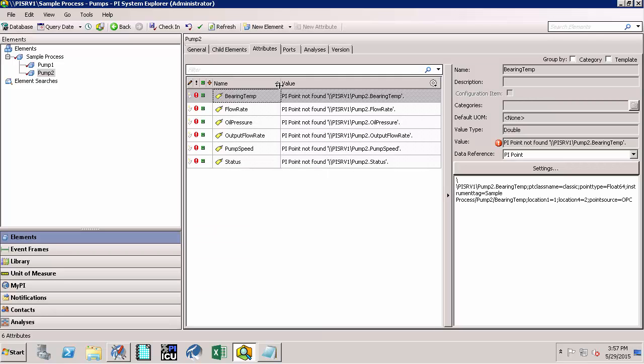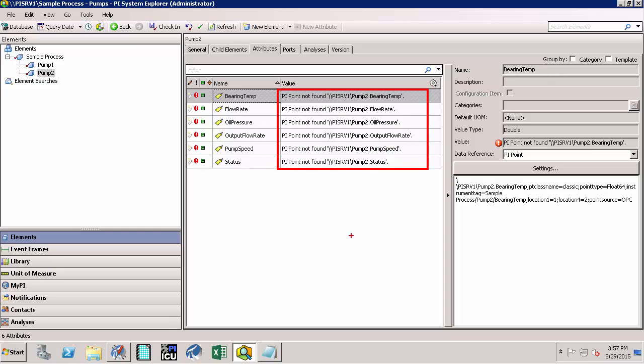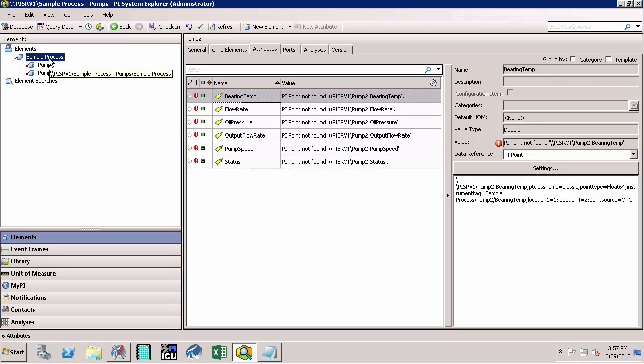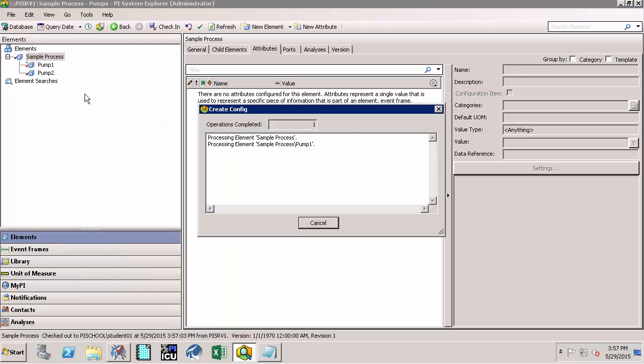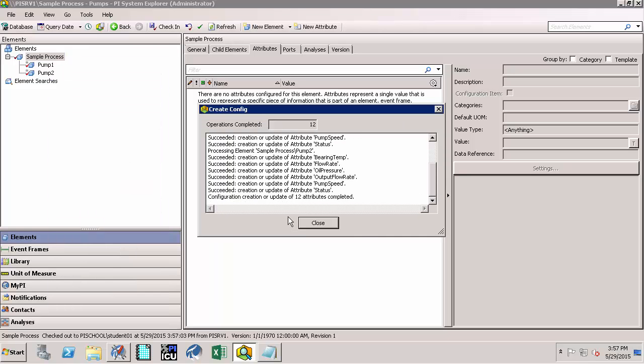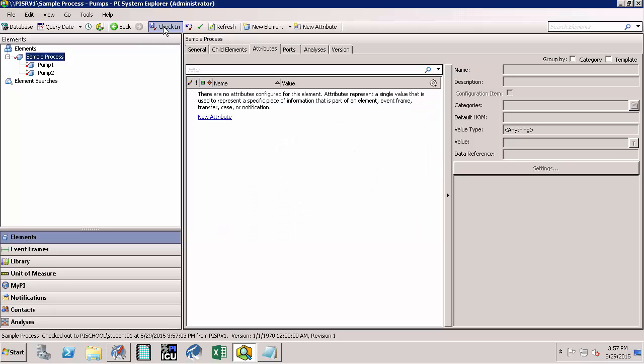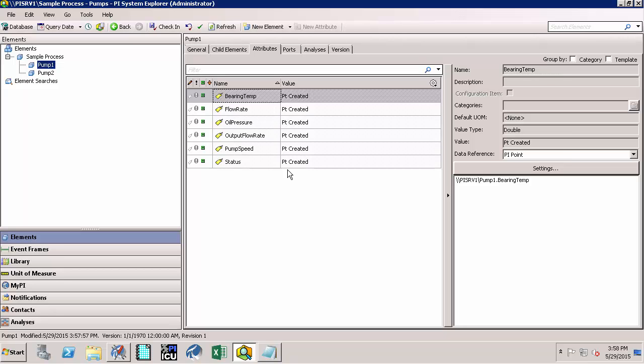Now let's go to the Attribute tab — we would note none of the PI Tags have been created yet. To create the PI Tags, right-click on Sample Process and say Create or Update Data Reference. By this process we have created all the tags associated with all the attributes for Pump 1 and Pump 2. Say OK, close, and we can check in the changes. Now if we click on one of the pumps we will see the PI Tags have been created, which says 'Point Created'.